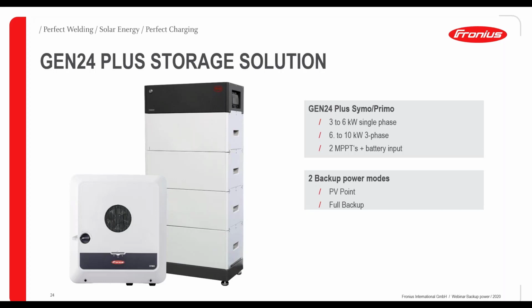That means there is the full backup mode as we know it, as we have explained before, very similar to the Symo Hybrid, no big difference, basically the same wiring required. But we also have a PV Point, and the PV Point is an easier version of the backup power mode. So for all customers who don't want the additional wiring and backup power switchover, because it's maybe too high a cost for them or too difficult, you can offer the PV Point as well. I will explain on the next slide what it is and how it works.